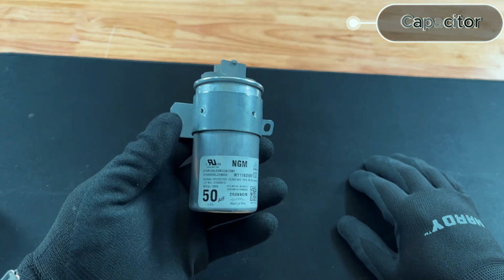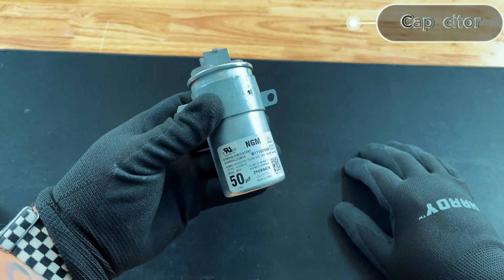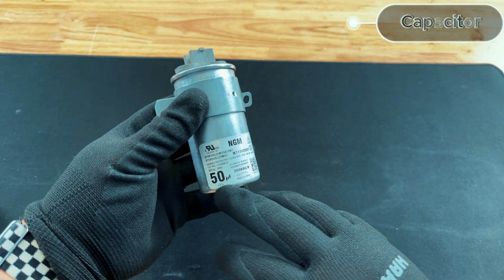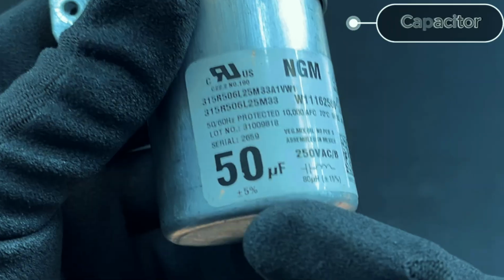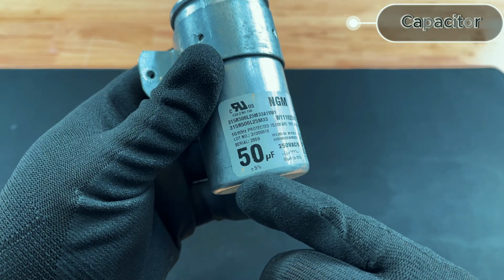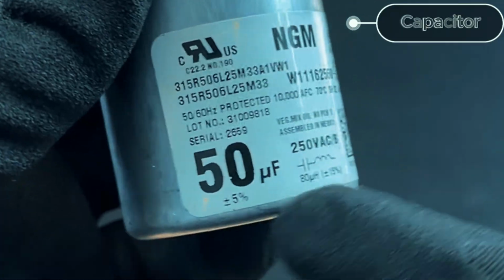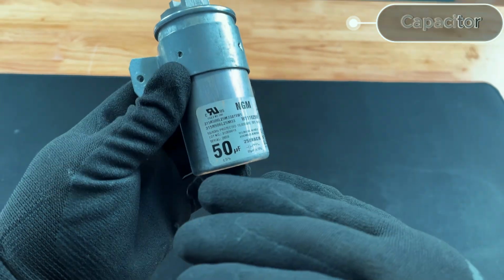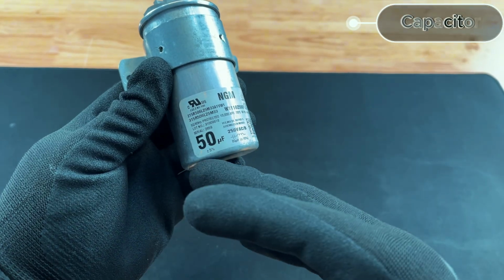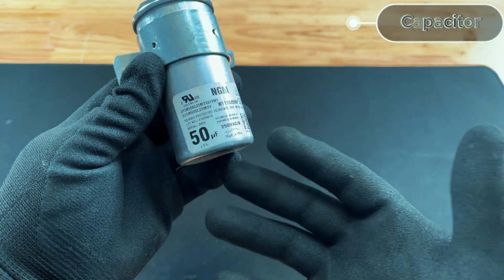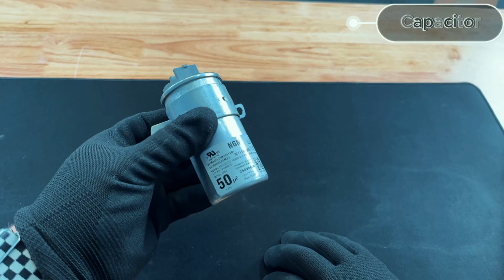All right, so let's talk about tolerance. When you're testing a capacitor, is 50 what you want to see every time? Is 49 a bad capacitor? Is 51 a bad capacitor? You kind of have to understand on the capacitor, they'll tell you what your tolerance is. On this one here, you can see it's plus or minus 5%. That means 5% of 50 is going to be around 2.5 microfarads. So that tells me anywhere between 48 to 52, I'm within range. So it's important to check your capacitor's tolerance. It's usually written really close to the microfarads rating. This one tested good no matter what we did. Make sure that you are checking your tolerance.